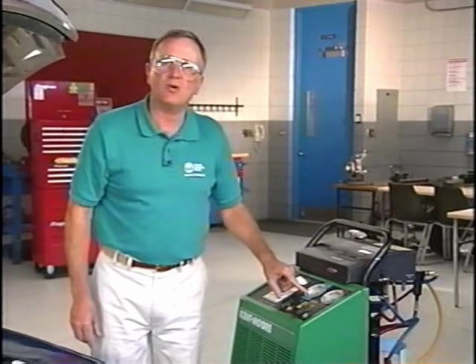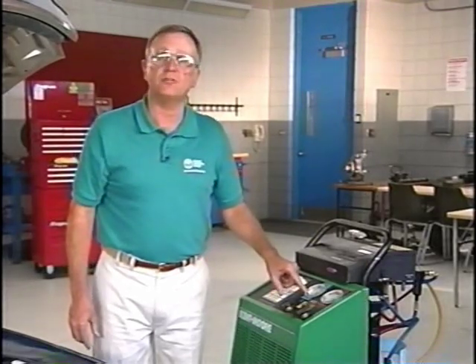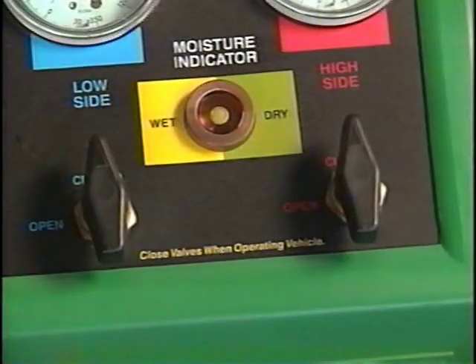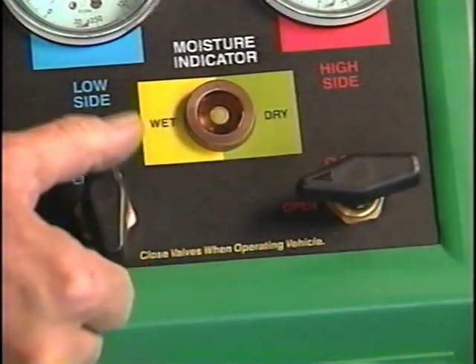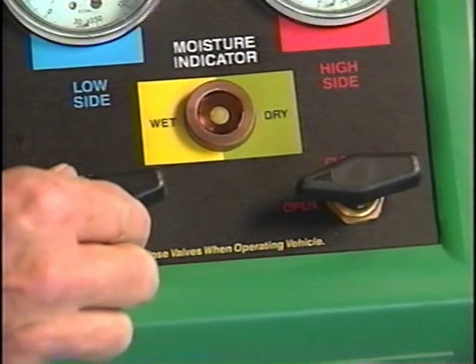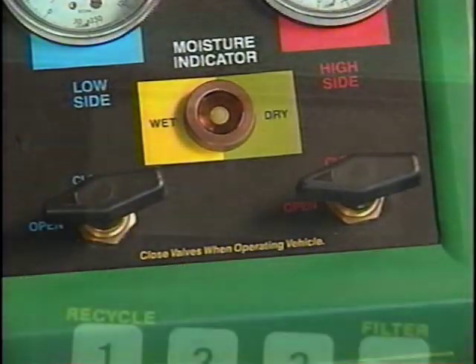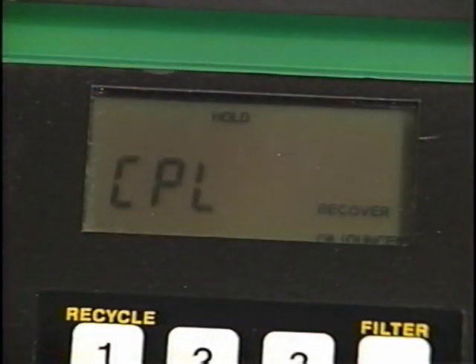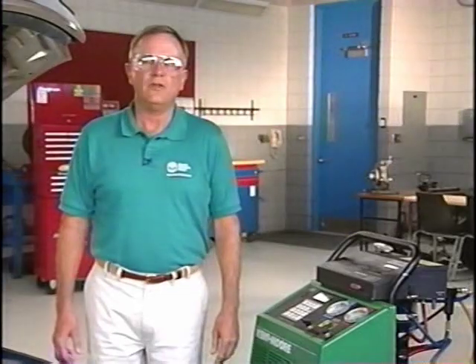If the pressure drops off, find and repair the leak before continuing. If the vacuum remains steady, open the high and the low side valves, push the continue button, and the evacuation process will continue. When the programmed time is up, the display will indicate complete. Now we've come to the actual charging portion of the operation.